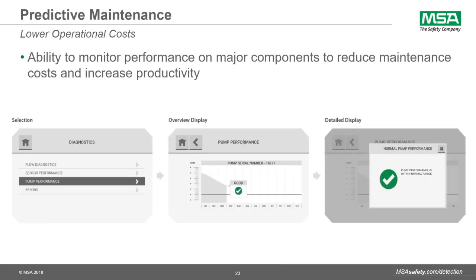Lower operating costs are always top of mind. We developed a feature called Predictive Maintenance that actually monitors the performance of the pump, sensor, and flow system. The system will send 2 levels of notification. The first gives a warning with troubleshooting techniques. The second alerts a user when a problem with that particular module occurs. So it will notify you if the system needs service.